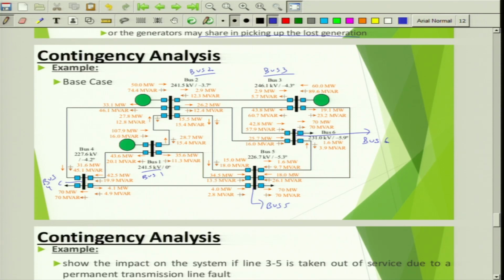At any given case, this is the voltage profile. You see here 240 kilovolts, typically 240, 246 at different buses, 230, 226 and 227, more than 220 kV. So it's a transmission level, right. The X by R ratio is far greater than 10 or 20. Let us assume the X by R ratio could be 10 or 20, or greater, and there is some typical line flow happening in terms of megawatt and MVAR. So this is the operating scenario.